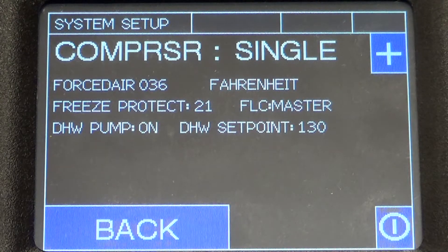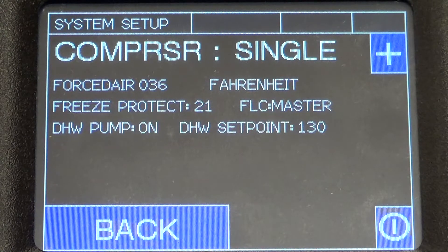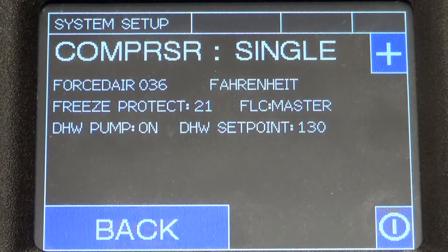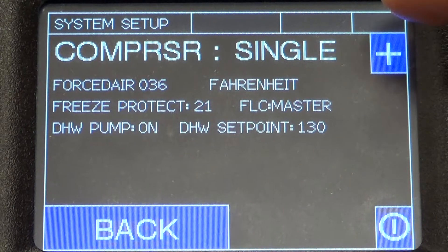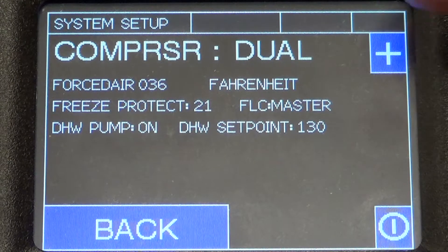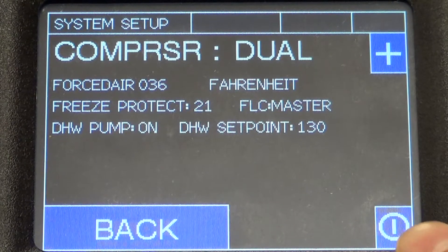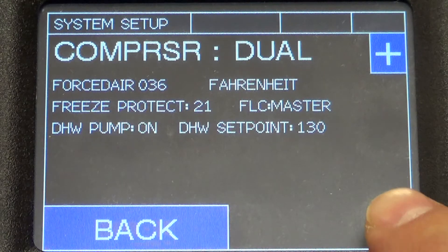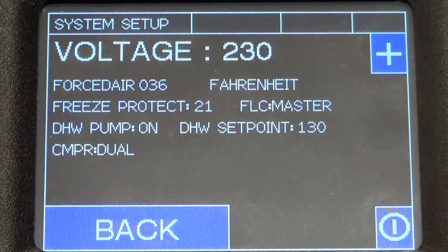On this next screen, you select if your compressor is a single or dual speed. If you're unsure, look at digit 8 in the model number on the serial plate — if it's a 1 or 3, it's single speed; if it's a 2 or 4, it's dual speed. Most forced air units come with a dual compressor, so we'll select dual.